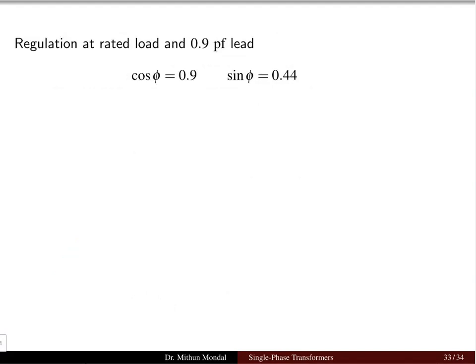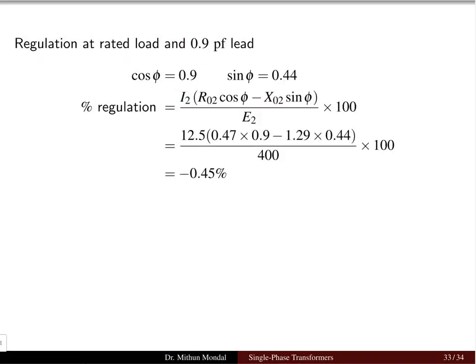Now regulation we have to find at rated load and 0.9 power factor leading. So cos phi is 0.9, that is the power factor, and sin phi is 0.44. In the percentage regulation formula which we have used, we have a negative sign because the power factor is leading. So this is the voltage drop I2 R02 cos phi minus X02 sin phi, and the base is E2, which we take to determine the percentage voltage regulation. So the voltage regulation comes to minus 0.45%.